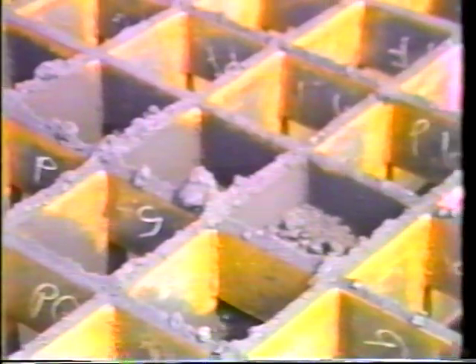Approximately in the center of the pad is an opening through which coke will be introduced into the system. The opening is approximately 9 feet by 10 foot and is covered by a grizzly which has 8-inch openings.